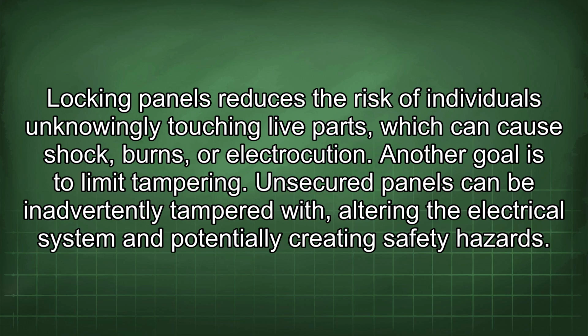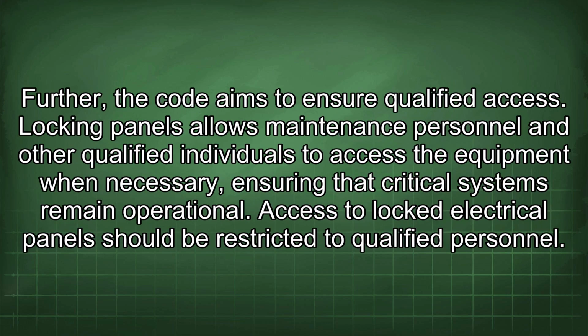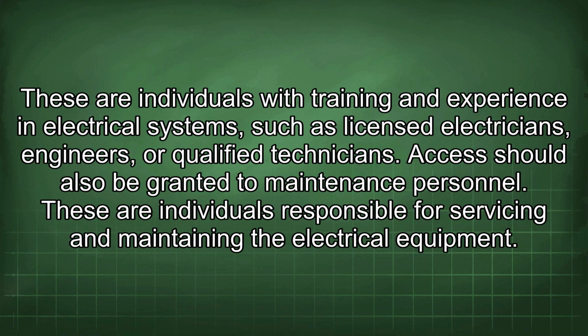Locking panels reduces the risk of individuals unknowingly touching live parts, which can cause shock, burns, or electrocution. Another goal is to limit tampering. Unsecured panels can be inadvertently tampered with, altering the electrical system and potentially creating safety hazards. Further, the code aims to ensure qualified access. Locking panels allows maintenance personnel and other qualified individuals to access the equipment when necessary, ensuring that critical systems remain operational. Access to locked electrical panels should be restricted to qualified personnel.